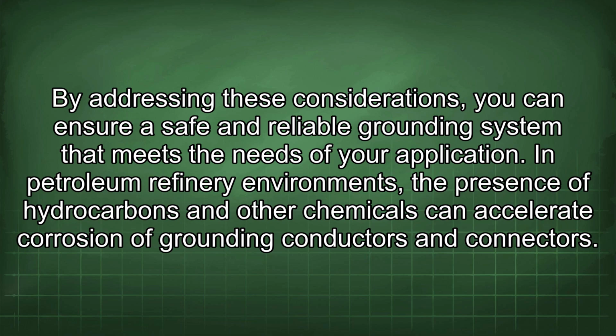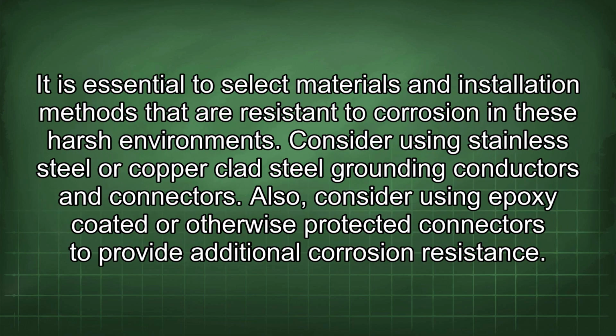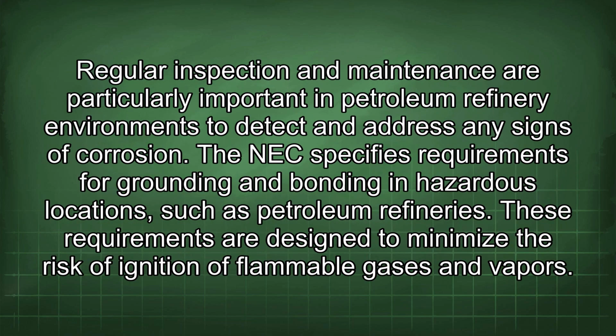In petroleum refinery environments, the presence of hydrocarbons and other chemicals can accelerate corrosion of grounding conductors and connectors. It is essential to select materials and installation methods that are resistant to corrosion in these harsh environments. Consider using stainless steel or copper-clad steel grounding conductors and connectors. Also, consider using epoxy-coated or otherwise protected connectors to provide additional corrosion resistance. Regular inspection and maintenance are particularly important in petroleum refinery environments to detect and address any signs of corrosion.